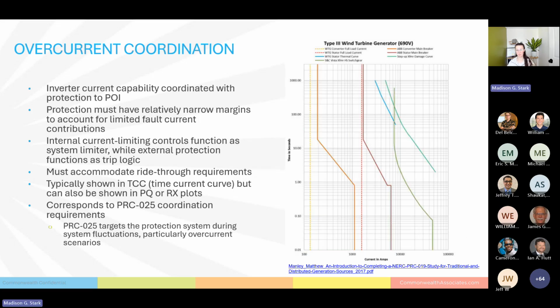This is just another example of a time current curve for a converter type resource, which is an inverter with an extra step. But the coordination that you're looking for is the same general thing, where you're coming from the left over to the right, and you want to hit your full load current capabilities first before you hit your protection system. That's exactly what we see. So we hit our full load current right here, followed by the protection for that particular element of the wind turbine. This is a type 3 wind turbine.